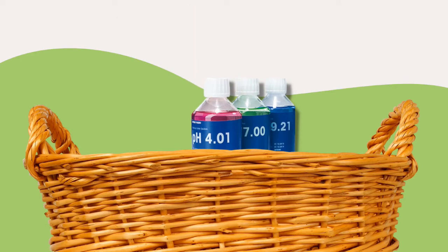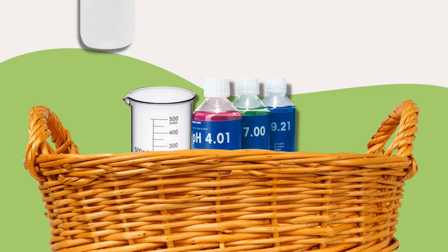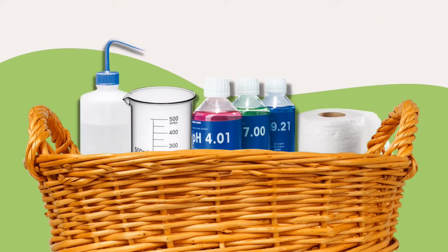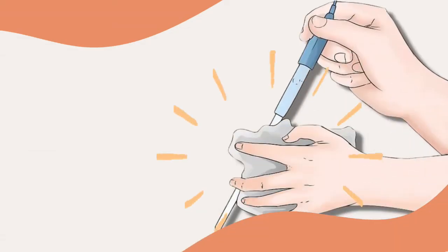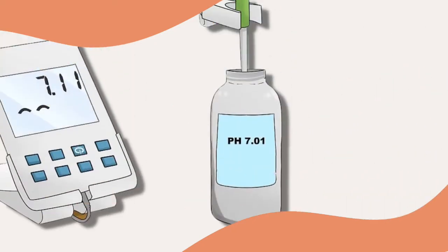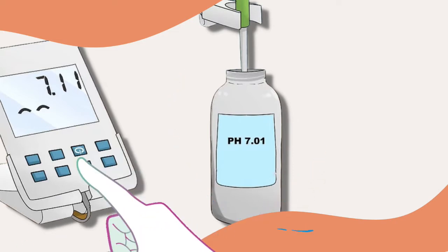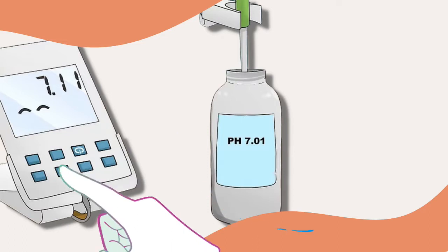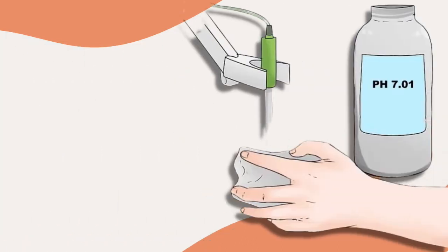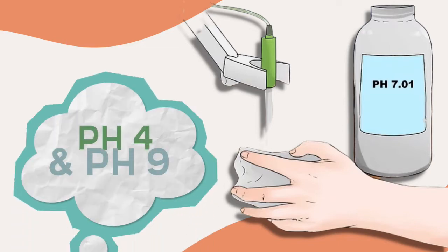Calibration of this instrument should be performed regularly to ensure accuracy and reliability of the device. To calibrate it, we need the buffer solutions, a beaker for our washings, a wash bottle, and tissue papers. We need to wash the end of the probe and wipe it with a lint-free tissue paper. After doing so, we can dip it in the pH 7 buffer. Remember to always calibrate with pH 7 first. Once done, press the calibrate button, and when the meter accepts the value, it is time to wash again the end of the probe and wipe it with tissue. The same procedure can be done for buffers pH 4 and 9.